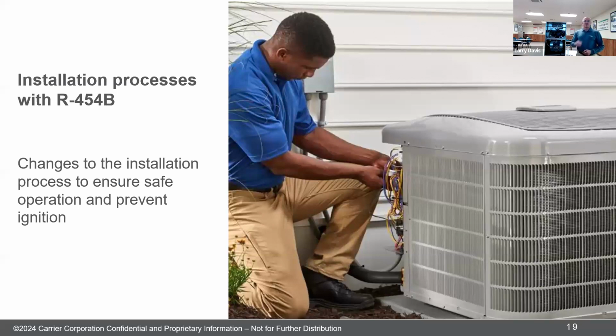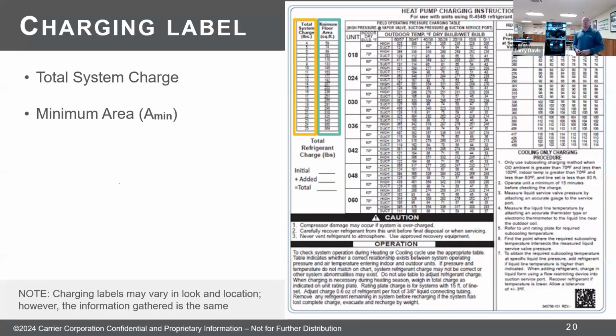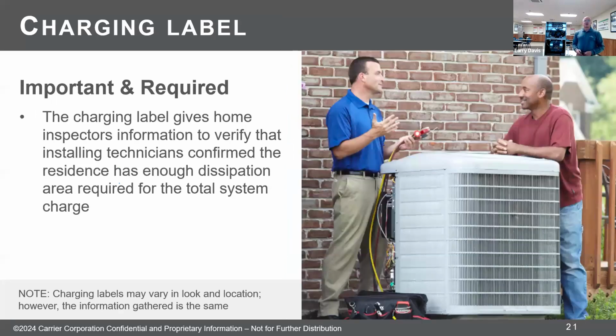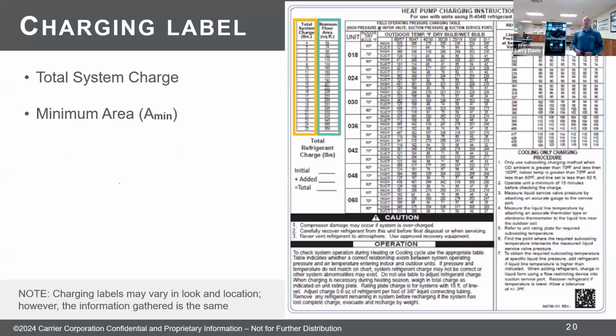So let's look at some of the installation processes for this new refrigerant and see how that compares to the 410A system. Again, I mentioned this before, you're going to be seeing these charts in all the outdoor units on the charging chart. There's a section down below the main chart that tells you, that's where you'll write in the total system charge. So we'll talk about that in another slide, but you're still going to have your charging chart, your subcooling scale, things like that. That's all still going to be in the unit. Those practices haven't changed. You're going to still use that same process to check the charge of the system.